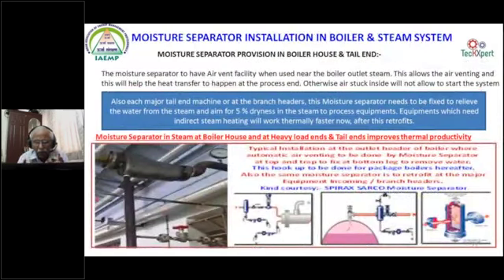Moisture separator is not only on the boiler header, but also on any of the bigger size machines where the steam dryness has to be maintained at 5%. 5% means 95% steam and 5% is the water that is allowed. In many of the industries where we have seen, they are using some 4 numbers of 6 ton boilers. We measured the steam dryness at the field. We found that it was only at 75 or 78%. 20% was the loss in the steam dryness. Moisture carryover was there in the steam.